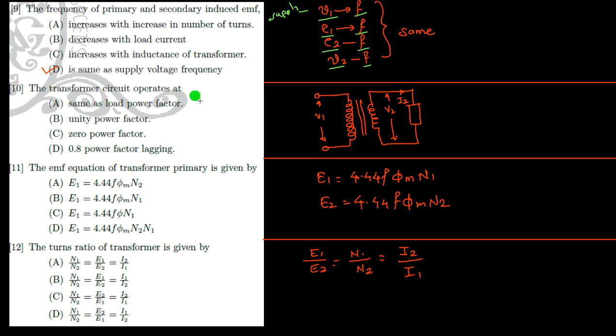The transformer circuit operates at a power factor same as the load. Suppose the load is of 0.8 power factor, then the power factor of the transformer is also 0.8. If the load is of 0.6 power factor, the transformer power factor is also 0.6. A transformer doesn't have its own power factor; whatever the load power factor is, it works on that. So it is the same as the load power factor.